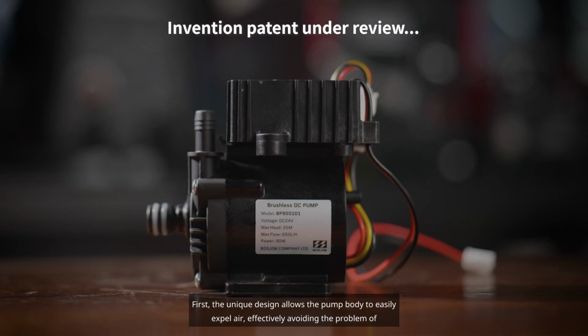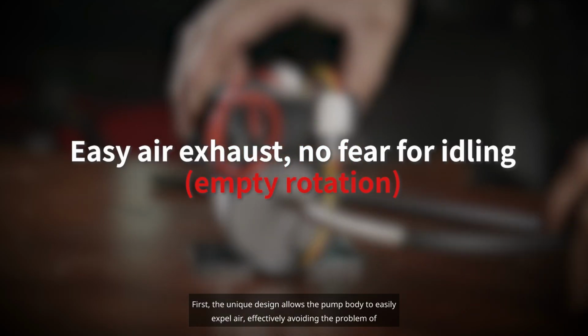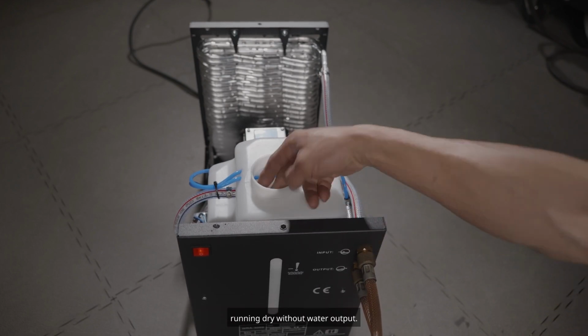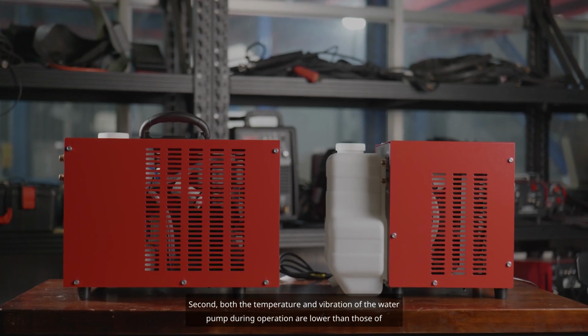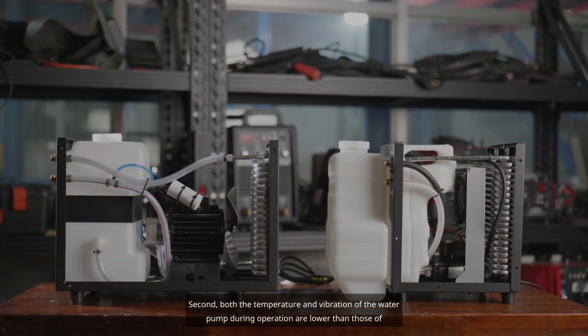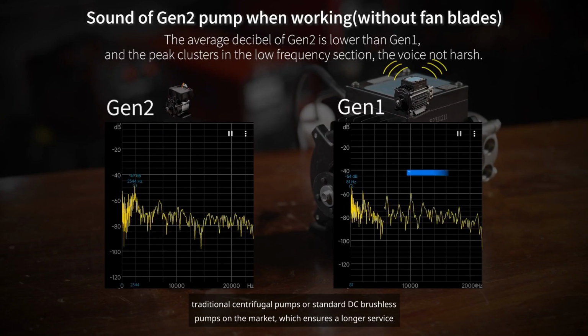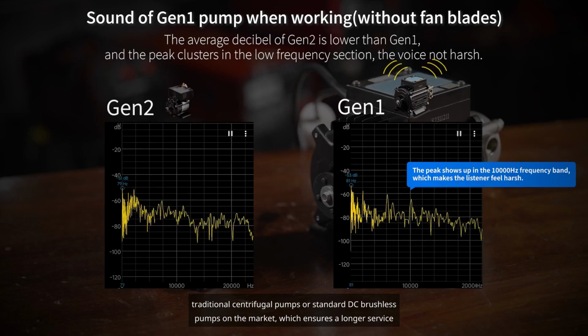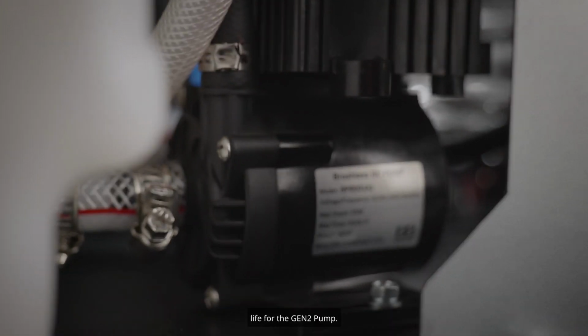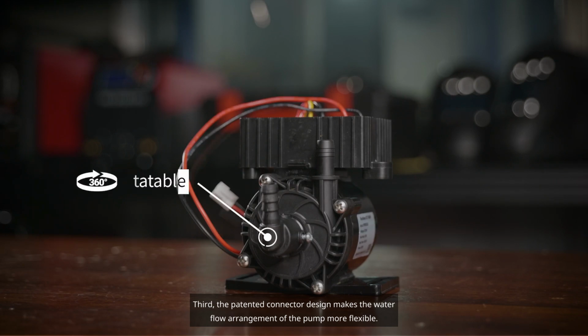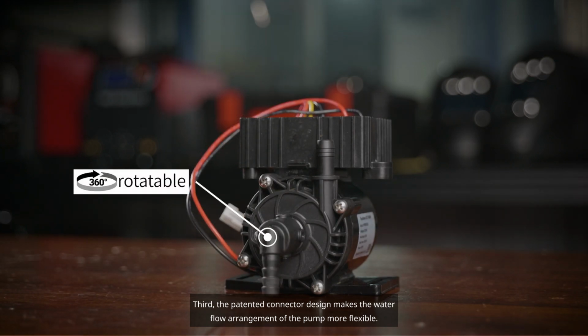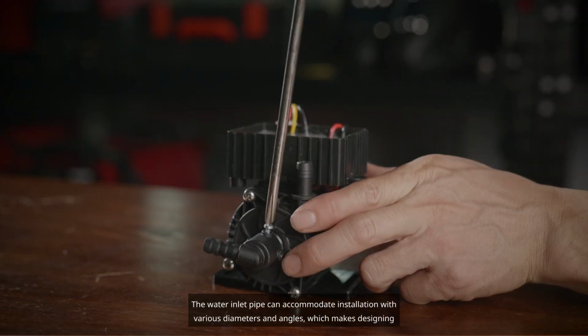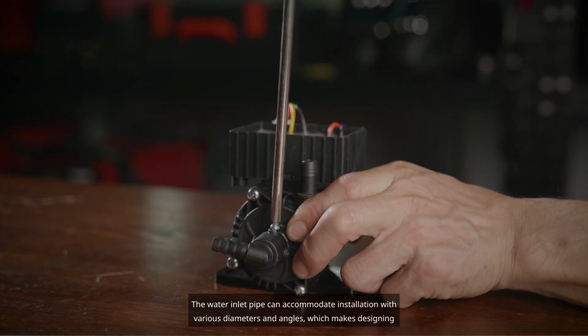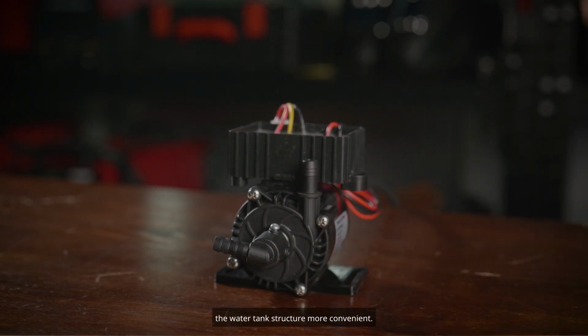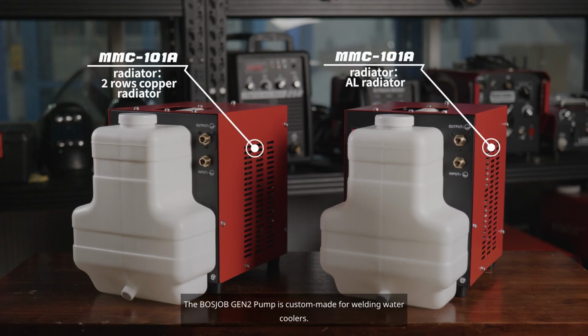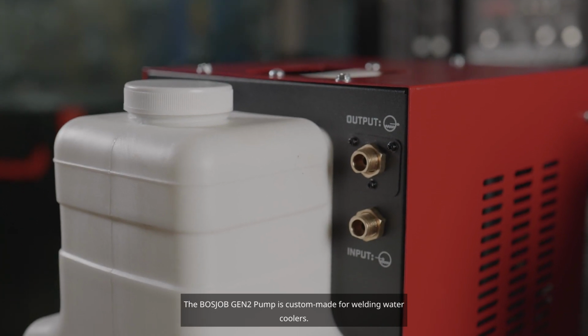First, the unique design allows the pump body to easily expel air, effectively avoiding the problem of running dry without water output. Second, both the temperature and vibration of the water pump during operation are lower than those of traditional centrifugal pumps or standard DC brushless pumps on the market, which ensures a longer service life for the GEN2 pump. Third, the patented connector design makes the water flow arrangement of the pump more flexible. The water inlet pipe can accommodate installation with various diameters and angles, which makes designing the water tank structure more convenient. The BOSJOB GEN2 pump is custom-made for welding water coolers.